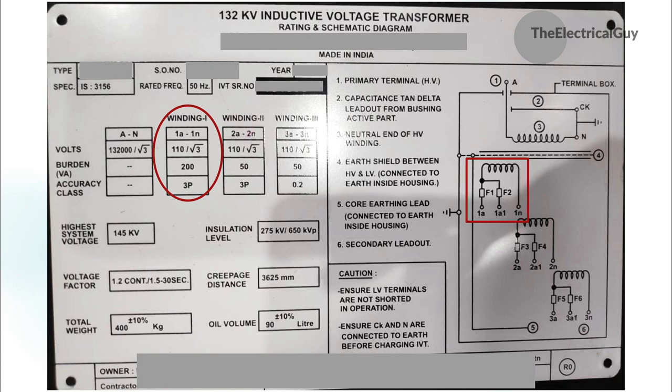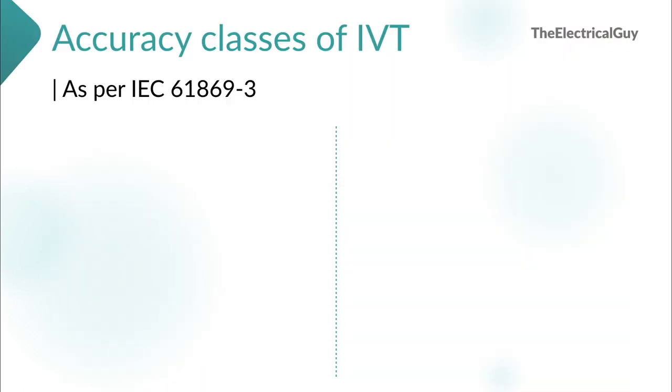For the first winding, the rated burden is 200VA, indicating you can connect up to 200VA across this winding. It is not good practice to specify a higher burden than required, as this will increase the weight of the IVT. Moving on to the fourth row of the secondary column — accuracy class.